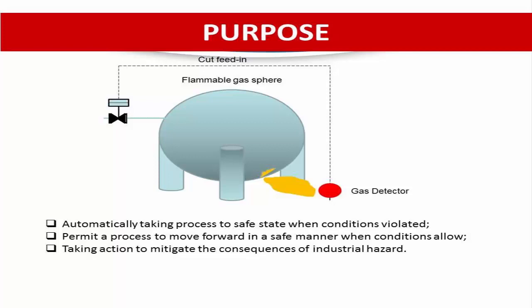The purpose of the SIS includes: first, automatically taking an industrial process to a safe state when specific conditions are violated; second, permitting a process to move forward in a safe manner when specific conditions allow, as a permissive function; or taking action to mitigate the consequences of industrial hazards. So the responsibilities of the SIS cover shutdown function, permissive function, and consequence reduction or mitigation function.